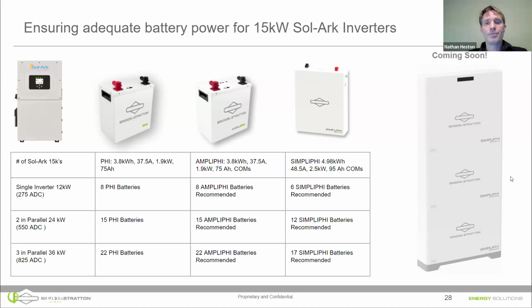In terms of our 4.98 or 5 kilowatt hour SimpliPhi batteries, these are the outdoor rated wall hung batteries. You would need 6 of these batteries. We recommend 6 of these batteries to get the full output capabilities of the Sol-Ark 15k, 12 for 2 parallel systems, and 17 for 3 parallel systems.